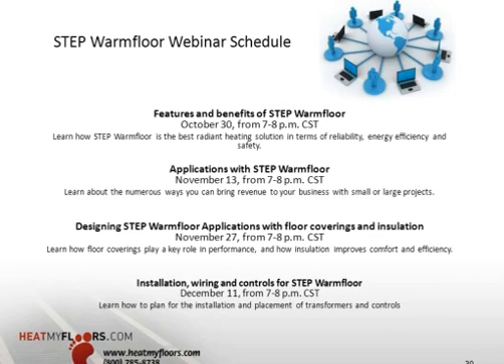So you'd use a thermostat maybe where a forced air heating system is the primary heat source, and you'd use a thermostat maybe with a floor sensor to control the ambient and the floor temperature, particularly the floor temperature, with a floor sensor independent from that of the forced air system. That way the systems don't fight and you can maintain comfort at your feet while perhaps the forced air heating is heating that same exact space. So thermostat's kind of up to you. We'll most likely design one for every application, but there's some applications that customers elect not to do so.